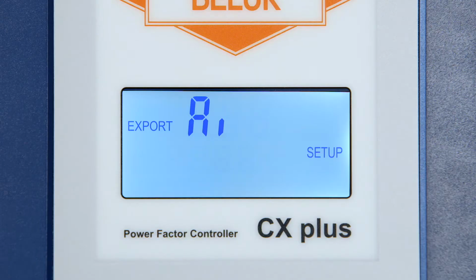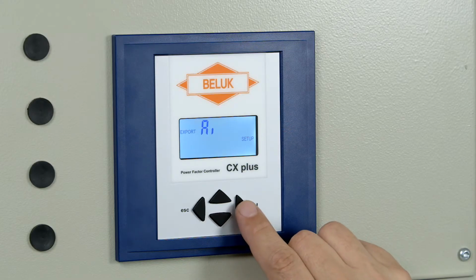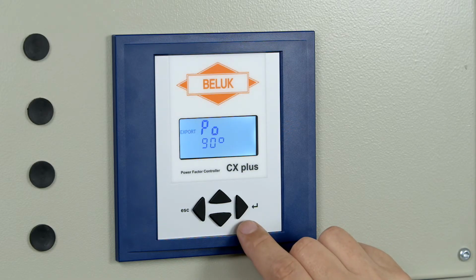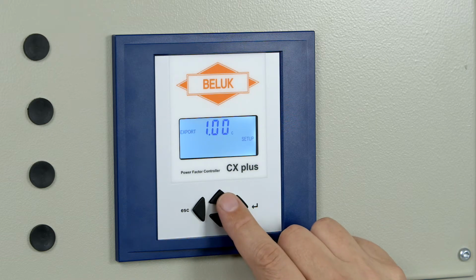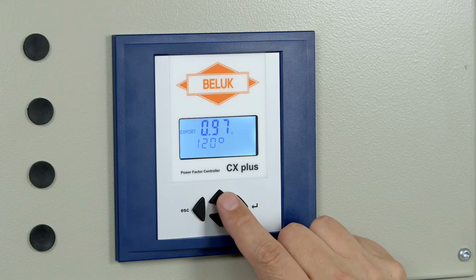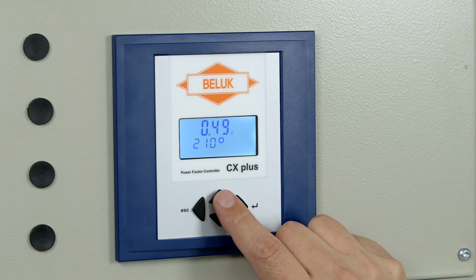If the automatic initialization AI is not selected, the phase offset PO must be entered manually. For this, the AI option is confirmed with No. This is followed by the input of the phase offset angle PO. During adjustment of the phase offset, the current cosine phi is shown in the display. This allows the current phase offset angle to be found easily and safely, an otherwise very error-prone process.